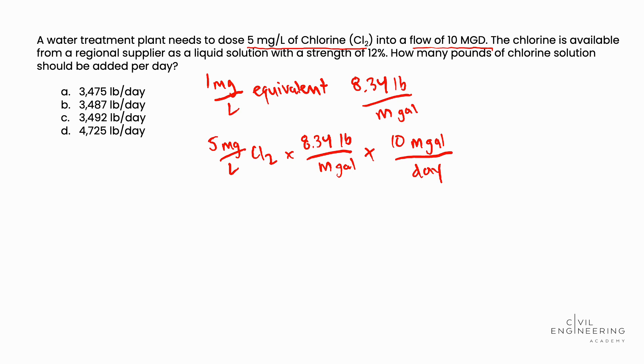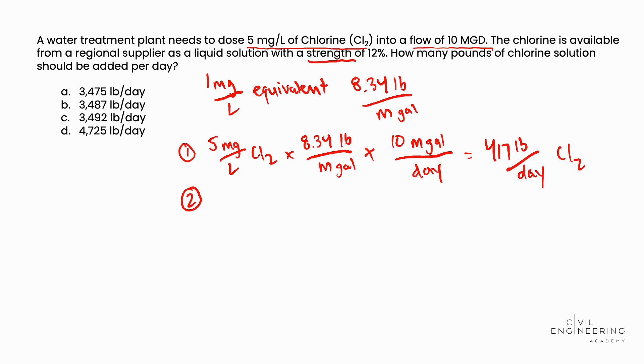We work this out and we get that there are 417 pounds per day of Cl2 chlorine that are needed. But that's not our answer — we'll call that step one. In step two, we need to look at the problem statement again, and we're told that the liquid solution has a strength of 12%. So the chlorine is actually diluted. We know 12% is equal to 0.12 in decimal form.